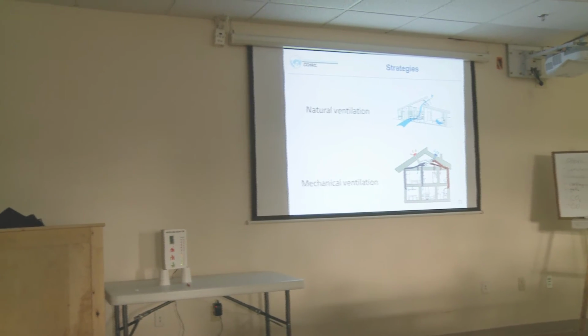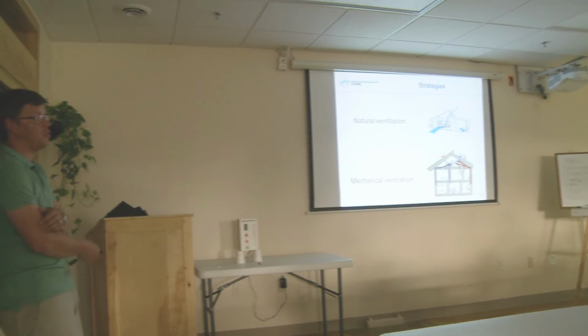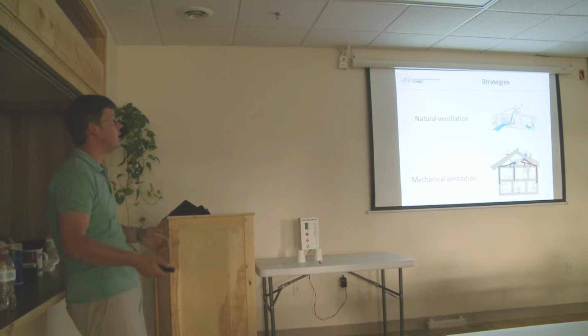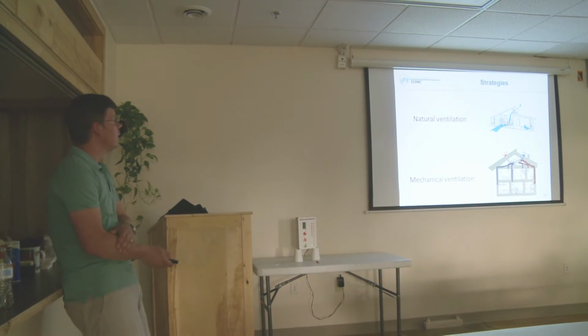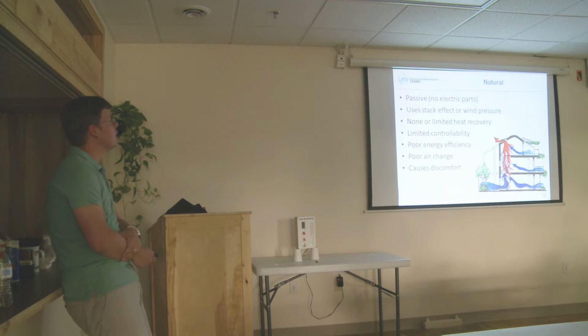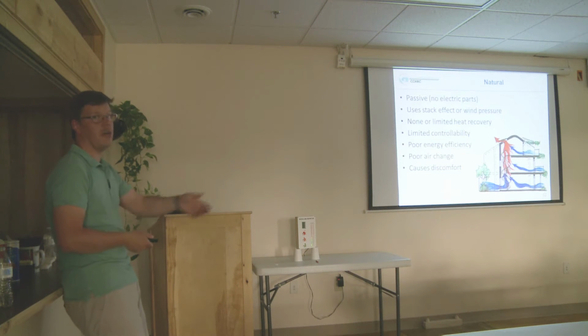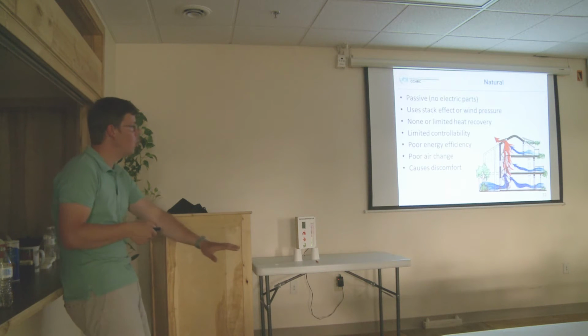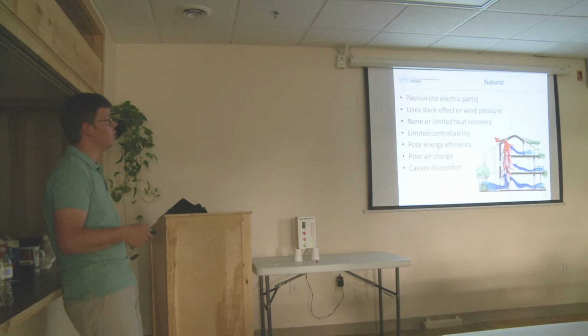Okay, so how do we ventilate? There are basically two principles. Either we do it naturally or we do it mechanically. If we do it naturally, that means passively, without electric elements and ventilators. We use a stack effect or wind pressure to drive the air through the house. That means the air comes in through an opening underneath the window or somewhere low, then it gets heated in the house, and then it leaves the house close to the roof.